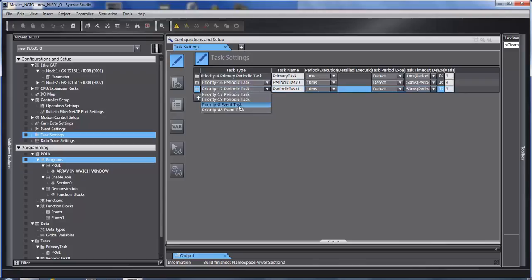You'll notice there is no interrupt tasks. The way the NJ deals with very fast I.O. is it has a time clock in all of its I.O. It timestamps when something happens and brings it back to the primary task with a timestamp.